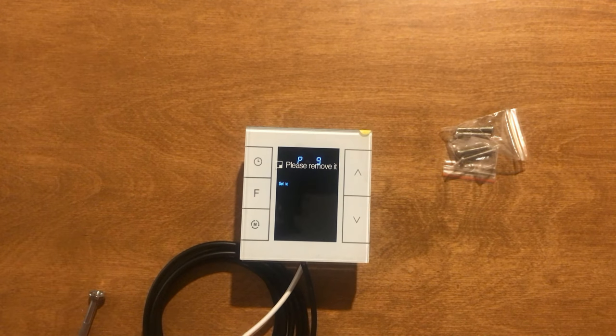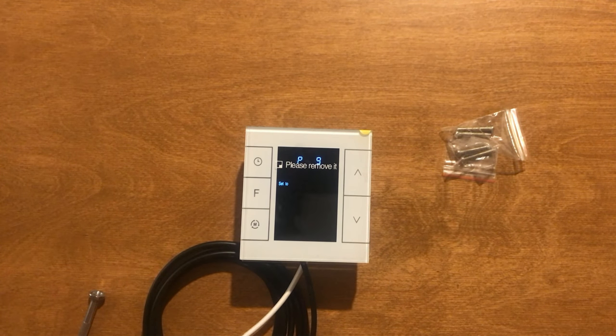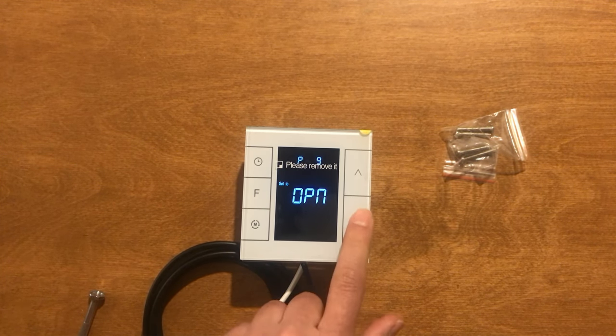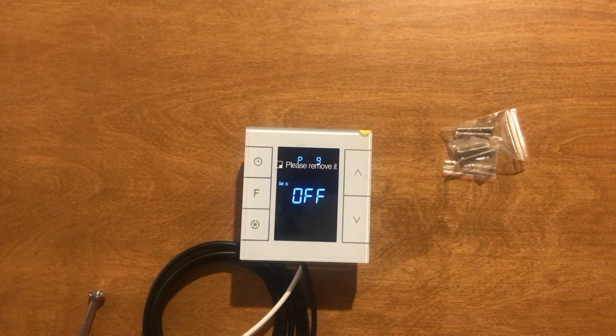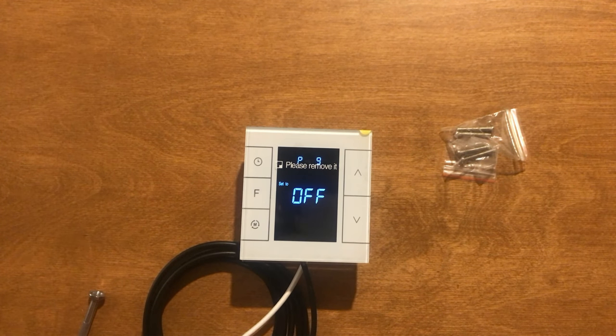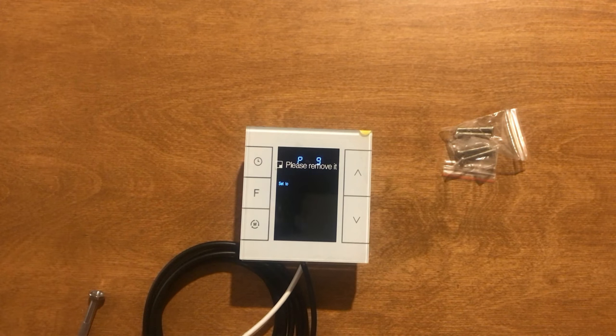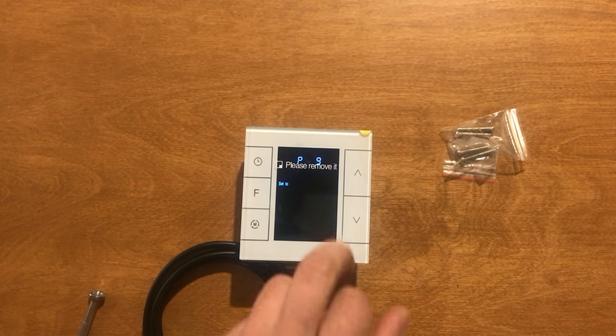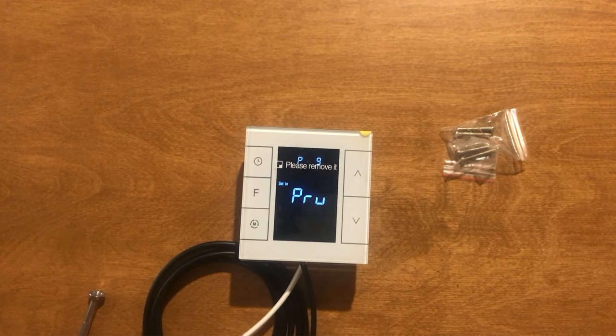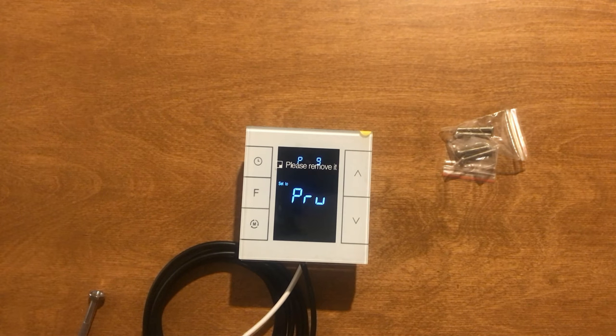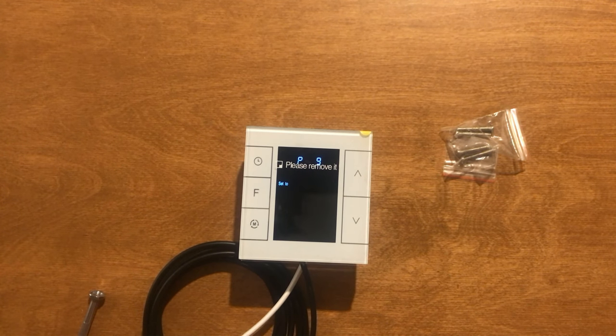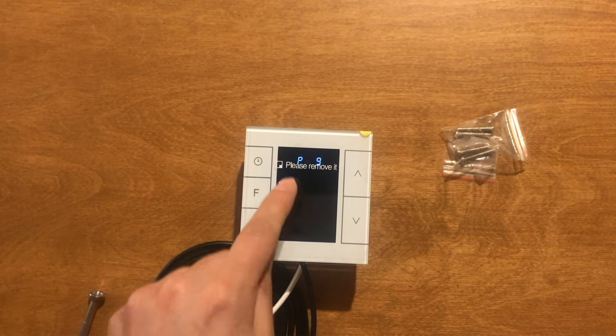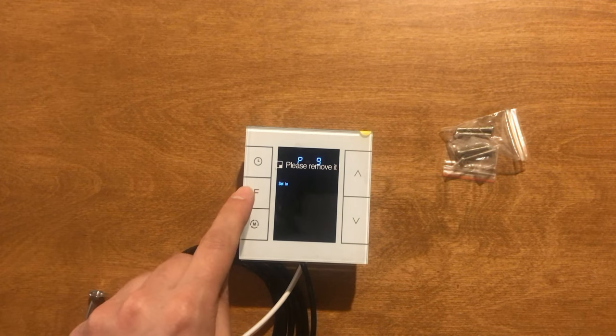P9 is power on state after power failure. Off means device turns to off state, OpN means device turns to on state, PrU means device turns to last state. I prefer to set this item to PrU.